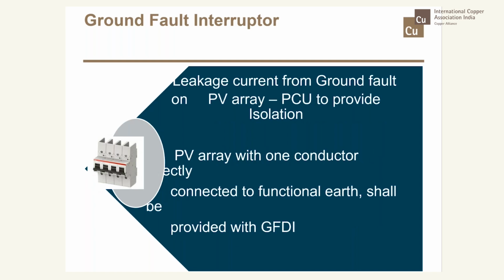Another important one is the introduction of a ground fault interrupter. Now the inverters available in our country, most of them do not have any ground fault detection and interruption. This is an American term. What we call here is nothing but the residual current device. These are never incorporated by the inverter manufacturer, and many times the integrator also does not include this component in his system.